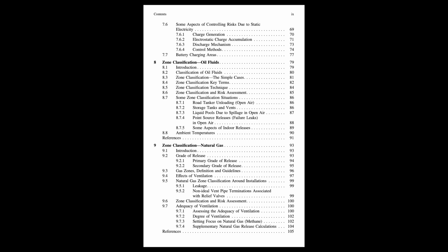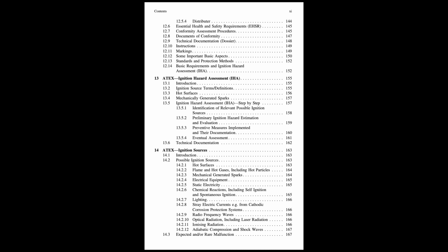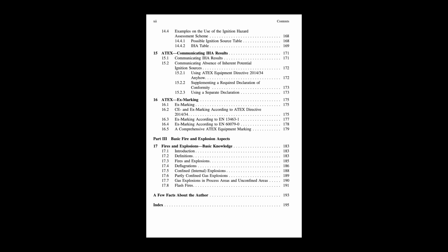And a key principle: where you have flammable atmospheres with low MIEs, you should strongly avoid using insulating materials, like standard plastics, for equipment construction, as they can lead to various types of hazardous static discharges. Even vessels with insulating linings need careful consideration for earthing. So good earthing and bonding are paramount, plus careful material selection and process control.